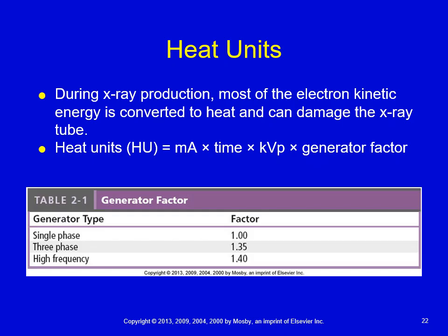I don't know if I can write on this. Let me see if I can. I can. 3-phase 6-pulse, as I mentioned, we are going to use 1.35. 3-phase 12-pulse, as I mentioned, we are going to use the factor 1.41.